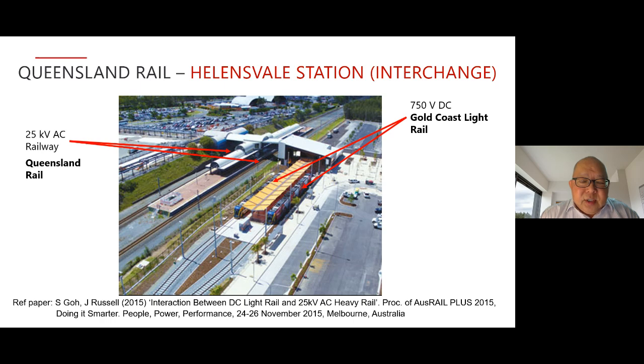We've got the station earthing and bonding, and then we've got the 25 kV earthing and bonding, and then you've got to manage the light rail as well. And the car park is actually fed from the station supply. So you can imagine that the earthing and bonding was quite challenging. So in the corridor, we have to create a sort of floating system if necessary, not bonded to either system, so that you can't touch two systems and get zapped. And along the track, you can see that the AC and DC are converging and running in parallel.